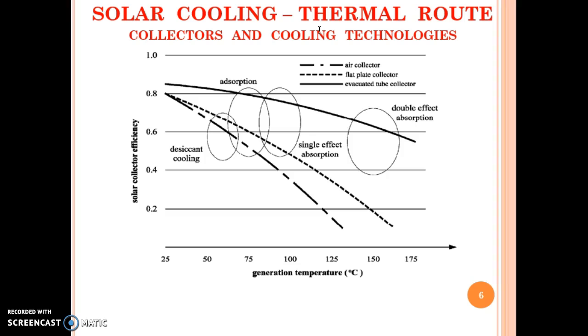Here solar cooling, the thermal route is shown. What are the different types of collectors which can be combined with different cooling technologies? So those domains are shown. The three lines here indicate the generator temperature versus solar collector efficiency. Generator temperature is nothing but the supply temperature from the solar collector. So as the supply temperature from solar collector increases, the losses from solar collector increase, so the efficiency goes down.